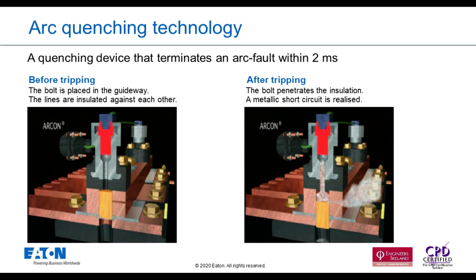Within Eaton's Arc-on system, the arc quenching technology is used in conjunction with the air circuit breaker, and this reduces the arc time present. This is possible using the fibre optical detection and current monitoring, and of course the very clever arc quenching device that you can see in the pictures. So instead of just trying to interrupt the arc with the circuit breaker, this type of system creates a dead short across the lines that mitigates the energy away from the arc and quenches the arc in a really quick time.